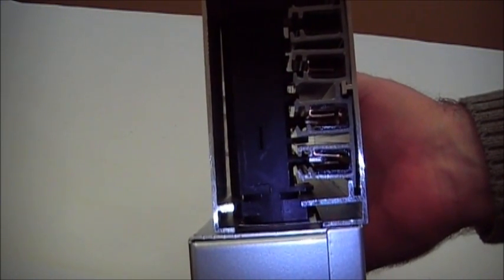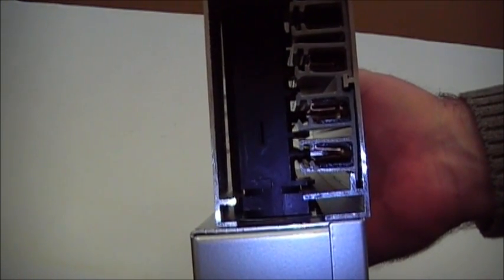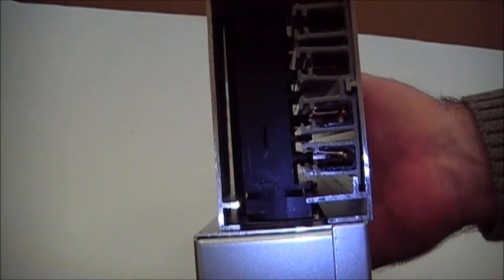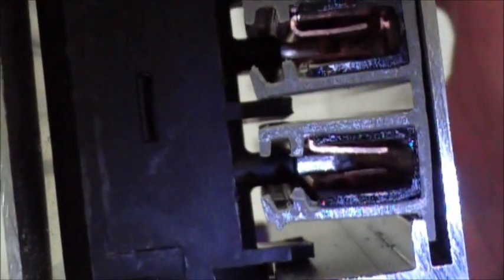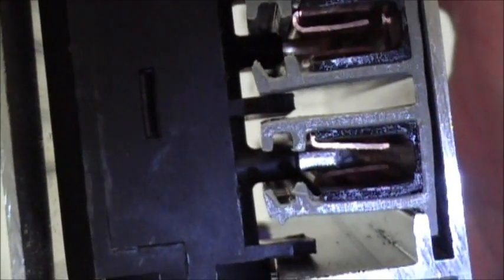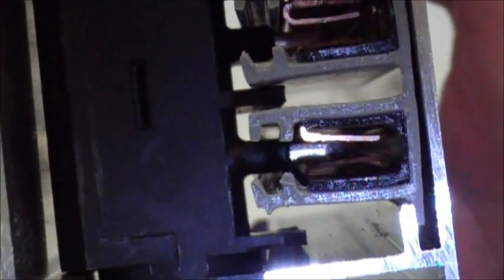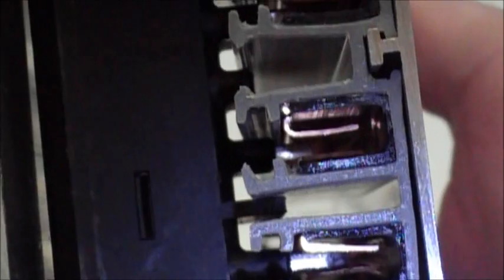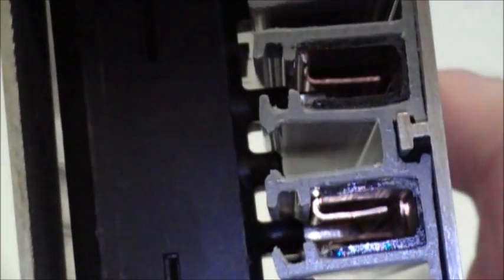Now we're taking a look at the end of the Starline track busway just so we can see how the paddle and the blades engage into the busway. So we'll zoom in to take a look at that design. As you can see, the blade is between the roll form copper that's providing some spring pressure constantly on the blade. So all the blades are engaged for each phase and neutral into the copper bus bar.